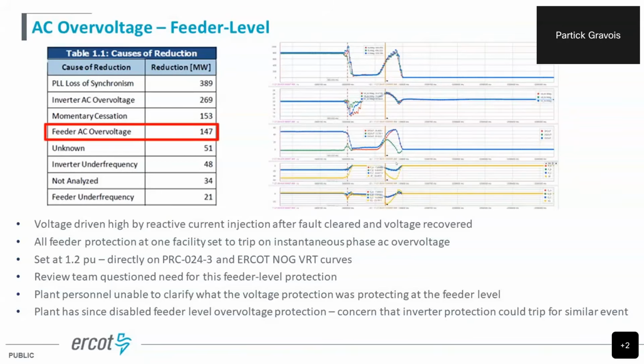NERC's been stressing this a lot: just because you go above that 1.2, you go outside those VRT curves, does not mean you have to trip. We prefer that you don't trip, actually. So they were able to disable this feeder level protection. But as we were studying the response from this unit, we realized, hey, just because you disable this feeder level protection, now you might have inverter protection that could trip off. You're still seeing this high voltage in your plant.